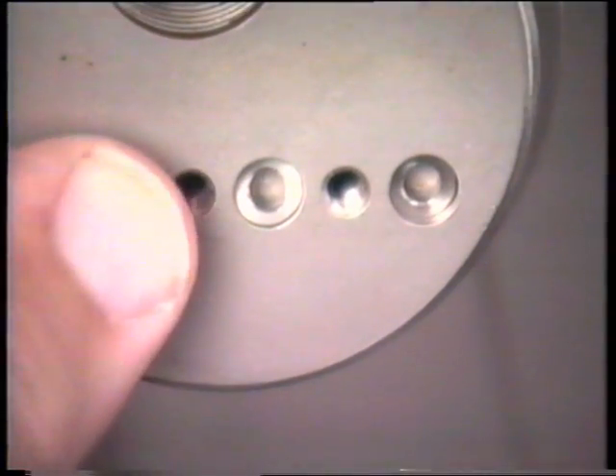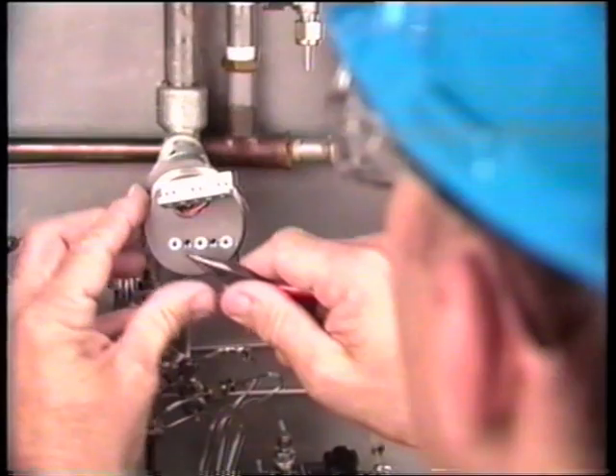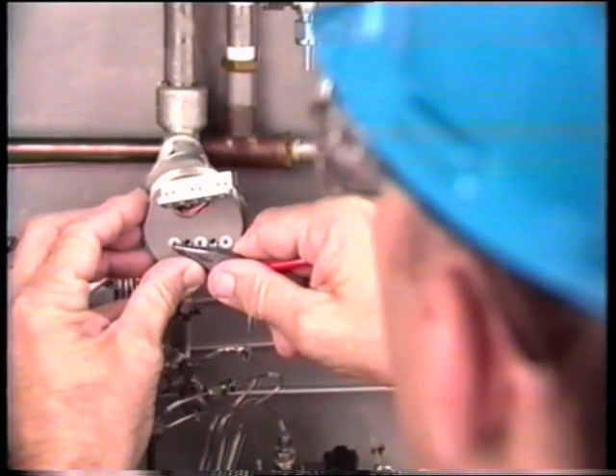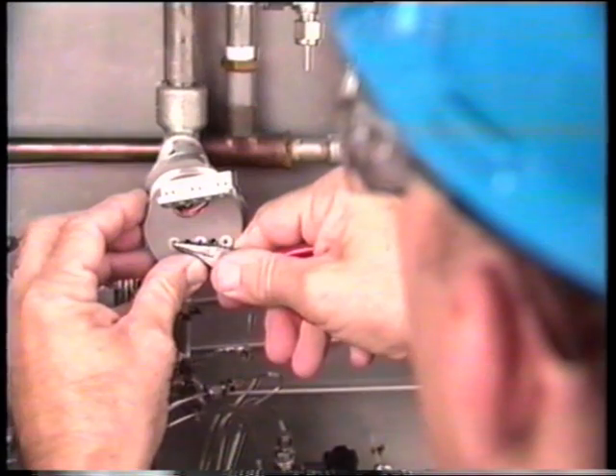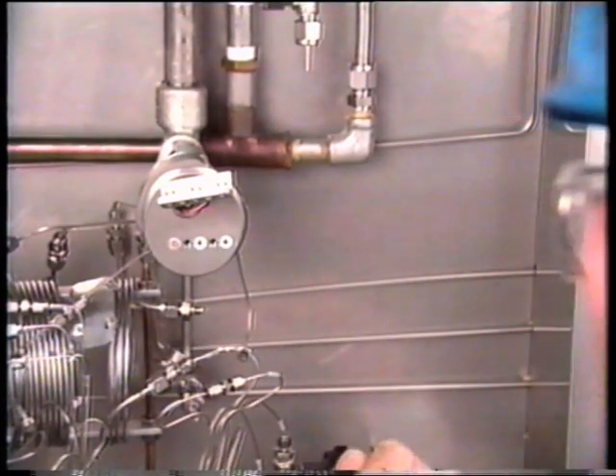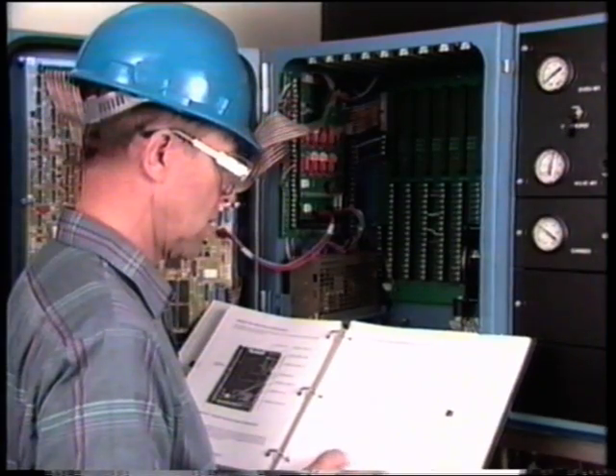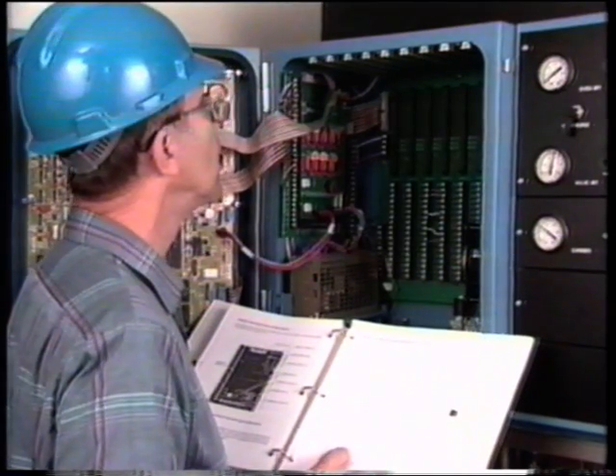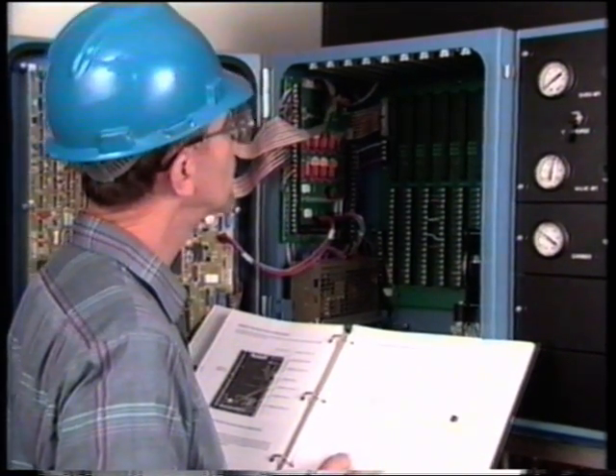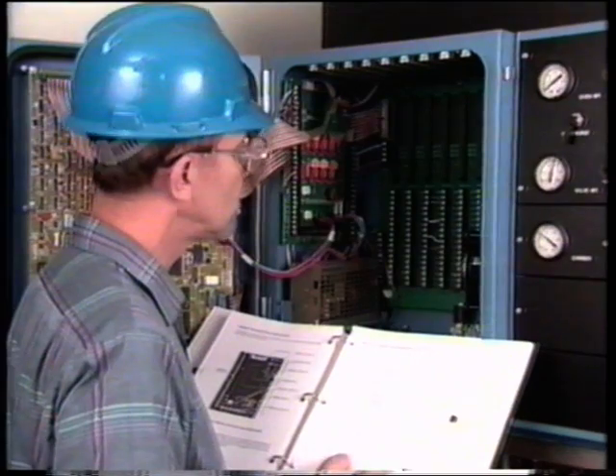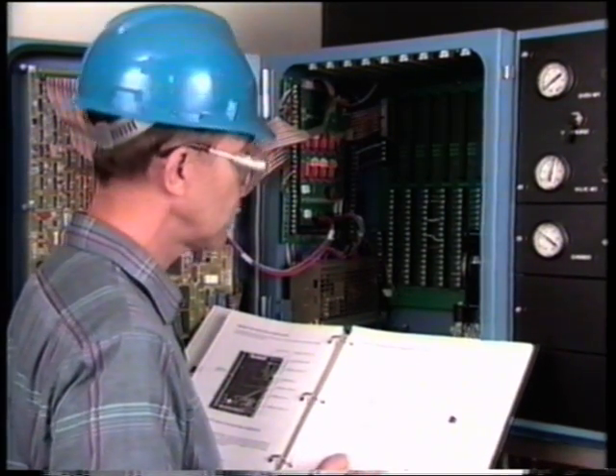Install the Teflon bushings on top of the inserts. Install new thermistors in the proper cavities. Replace the cover plate and solder the thermistor leads. Your workbook has additional information on thermal conductivity detectors. In the next segment, we'll review the maintenance for a flame ionization detector.